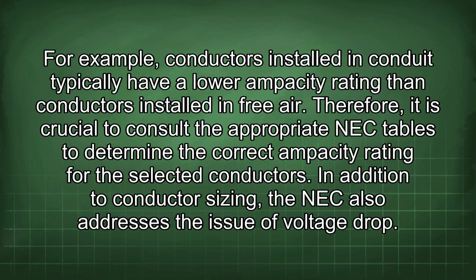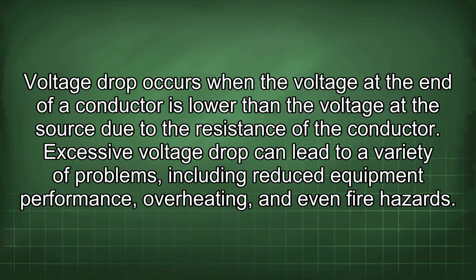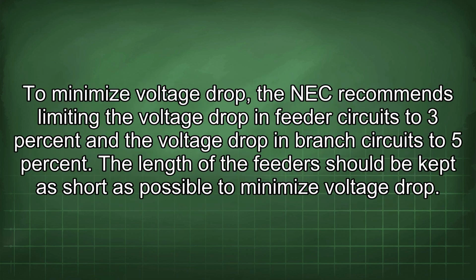In addition to conductor sizing, the NEC also addresses the issue of voltage drop. Voltage drop occurs when the voltage at the end of a conductor is lower than the voltage at the source due to the resistance of the conductor. Excessive voltage drop can lead to a variety of problems, including reduced equipment performance, overheating, and even fire hazards. To minimize voltage drop, the NEC recommends limiting the voltage drop in feeder circuits to 3% and the voltage drop in branch circuits to 5%.